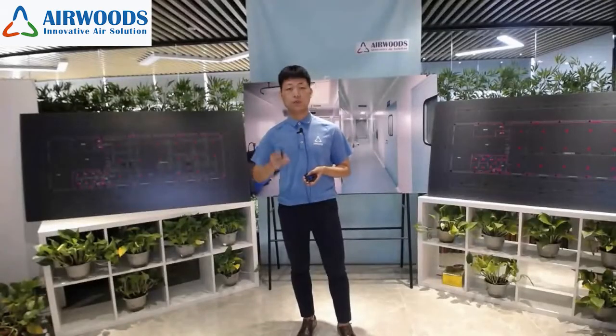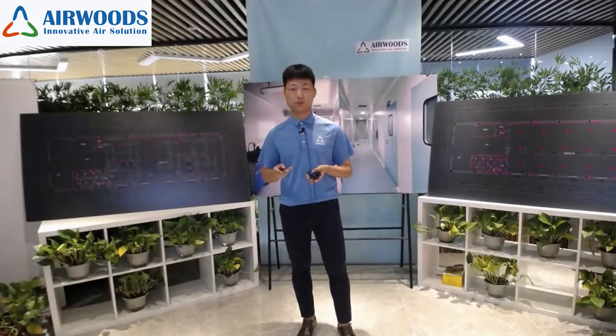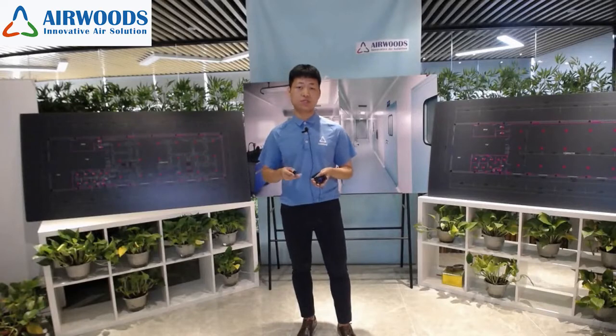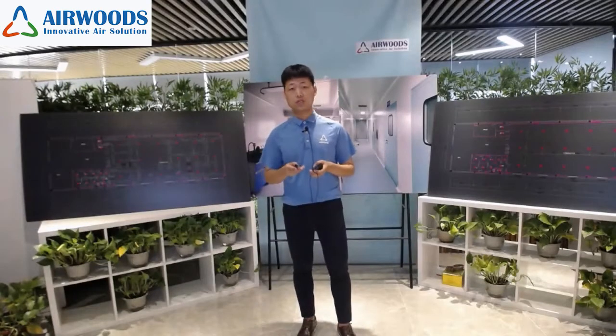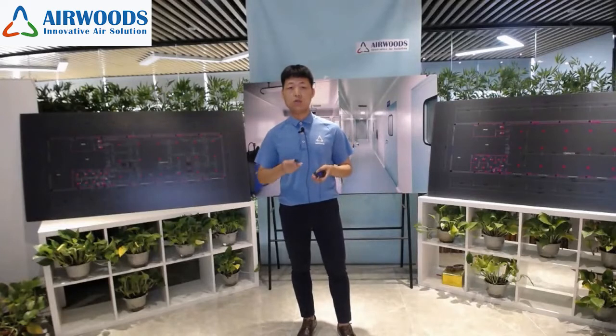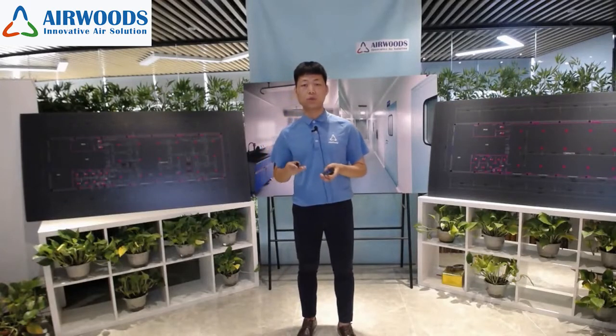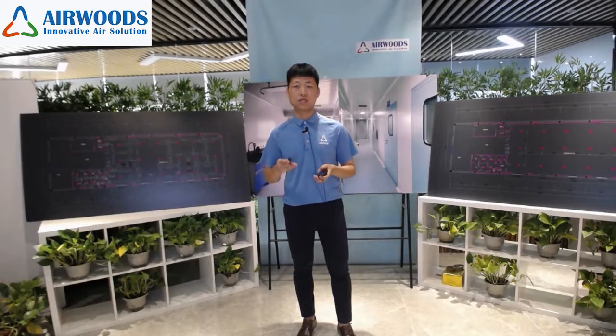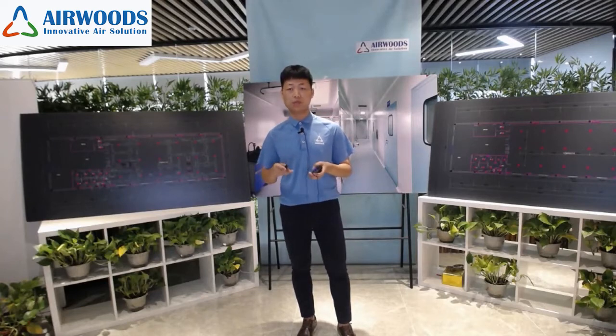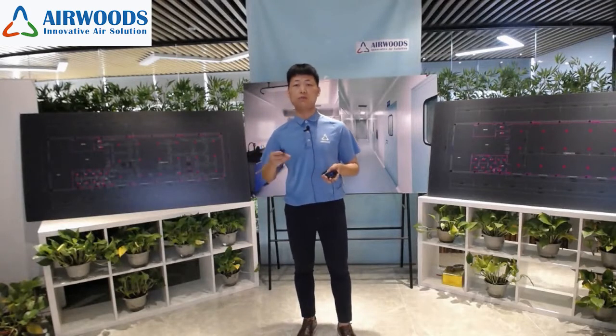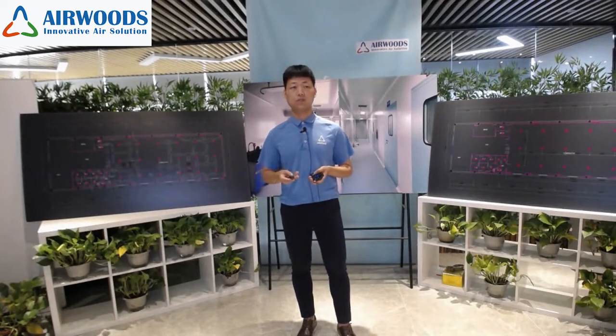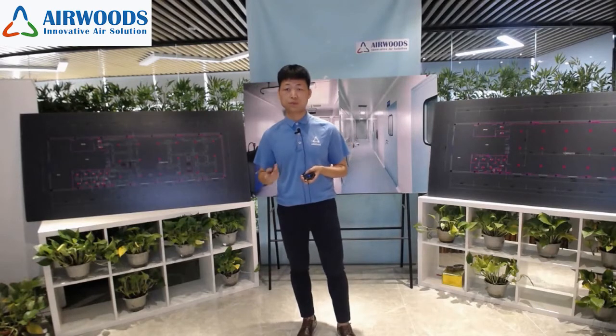The first one, supplying airflow in sufficient volume. We calculate the supply air according to the ISO standard air change rate, and also consider the room pressure requirements and the make-up air if there is exhaust in some specific rooms. The total supply air needs to have an additional 10% to 20% for the safety factor.